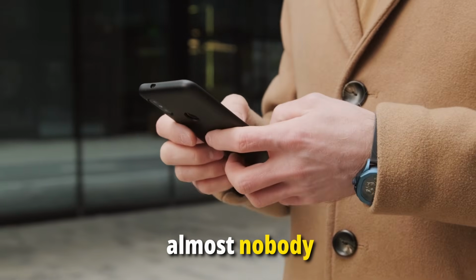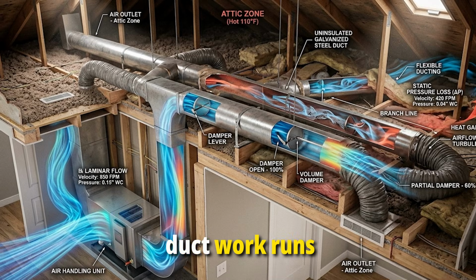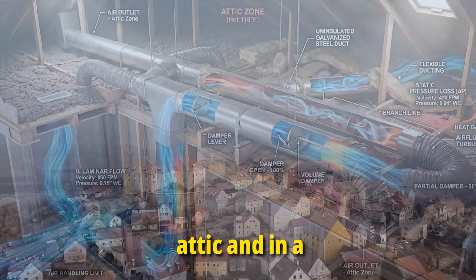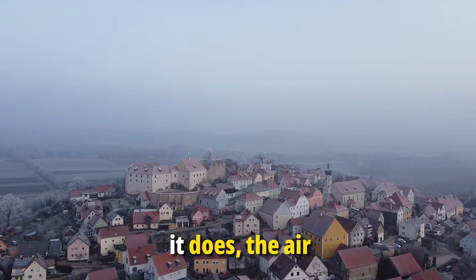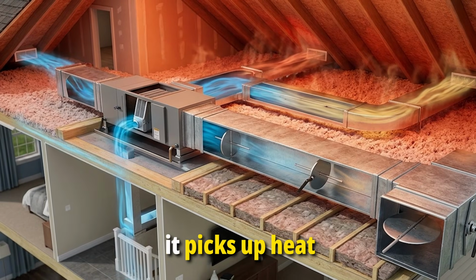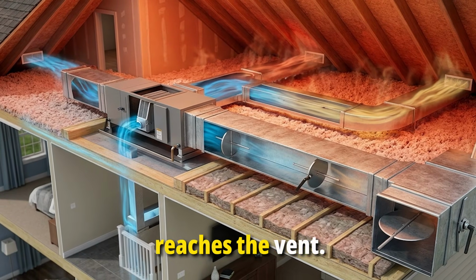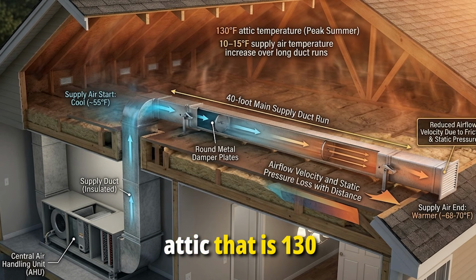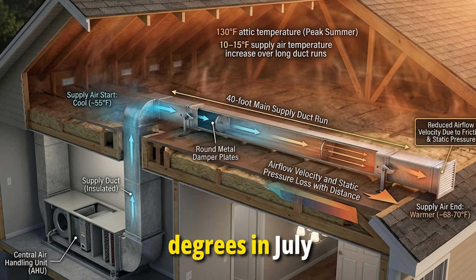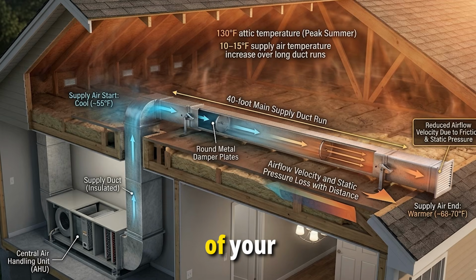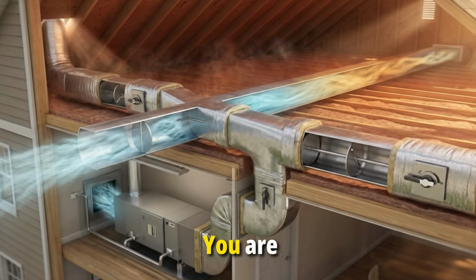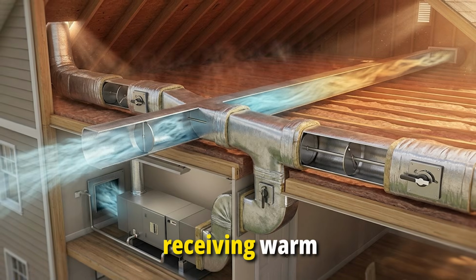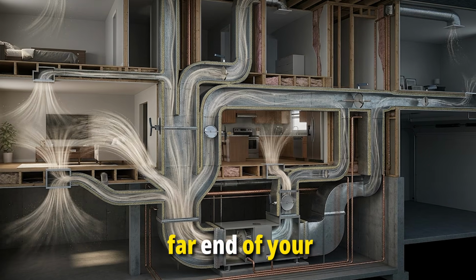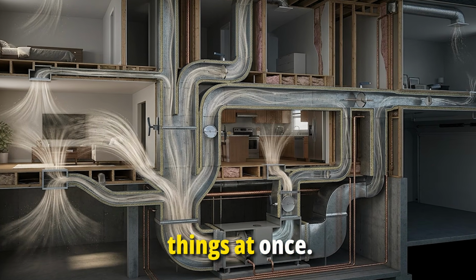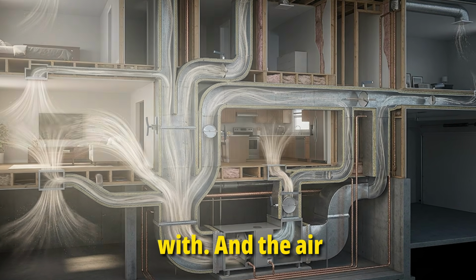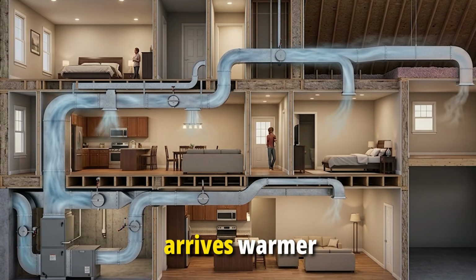And here is something almost nobody mentions. If your ductwork runs through an unconditioned attic, and in a huge number of American homes it does, the air traveling through it picks up heat before it ever reaches the vent. A 40-foot duct run through an attic that is 130 degrees in July can raise the temperature of your supply air by 10 to 15 degrees. You are sending cool air in one end and receiving warm air at the other. The rooms at the far end of your system are fighting 2 things at once. They are getting less air to begin with, and the air they do get arrives warmer than it should.